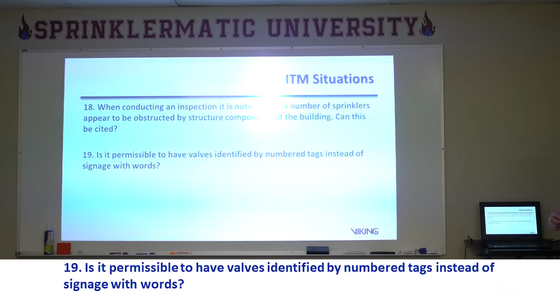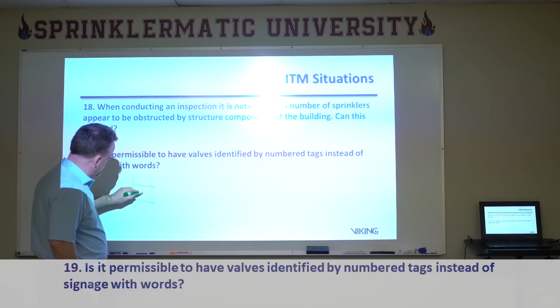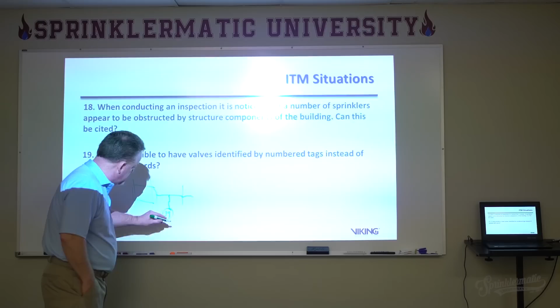Is it permissible to have valves identified by numbered tags instead of signage with words? You'll often see a control valve for a system. NFPA 13 says you have to have signage on all valves, identifying what they do. But in this case, there's a little chain with a tag that says 39. Is that permissible? Is that citable? Can that identify the valve? Yes, sure.